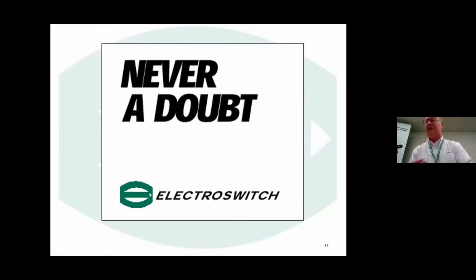Another style of switch is the raise and lower for a tap changer on a tap changer control. You might want to raise and lower taps on a transformer. So there's a function that we sell a lot of switches in, the local remote, or the raise and lower function. In bridge controls, we sell switches that are used for raising and lowering, dual leaf bascule bridge controls. So I would say those are the two most popular mechanical switches. And then of course there's the electrical version of those switches.